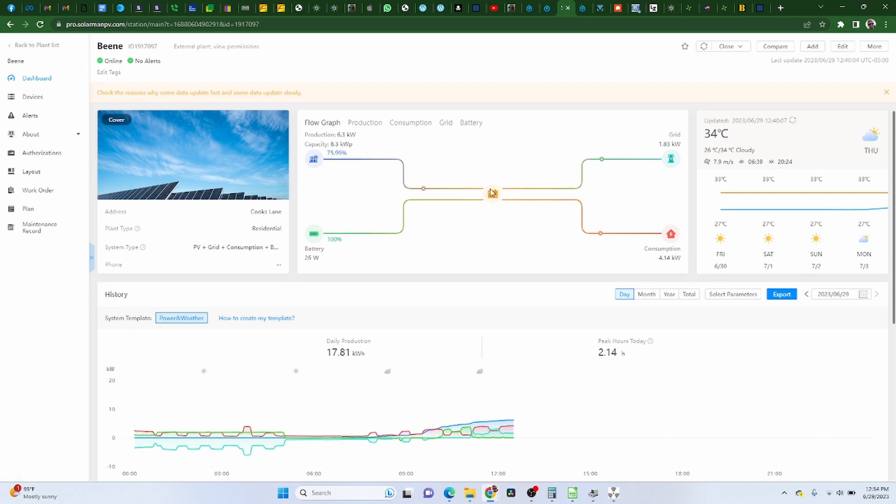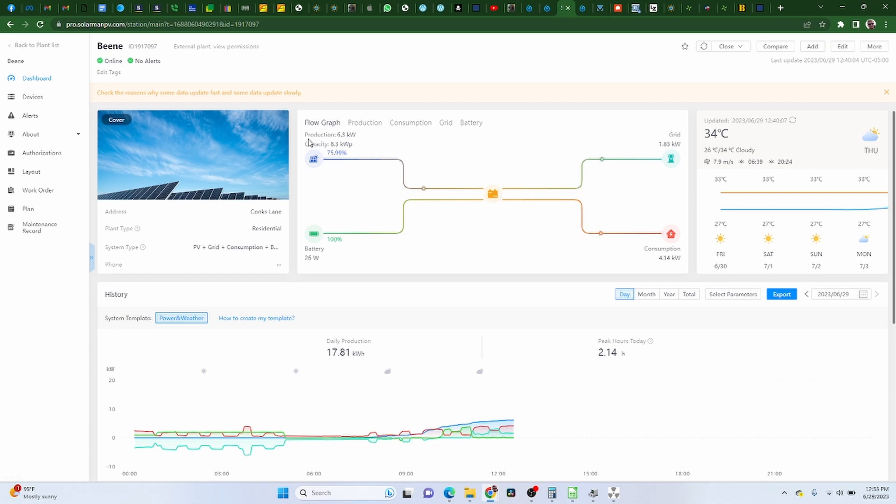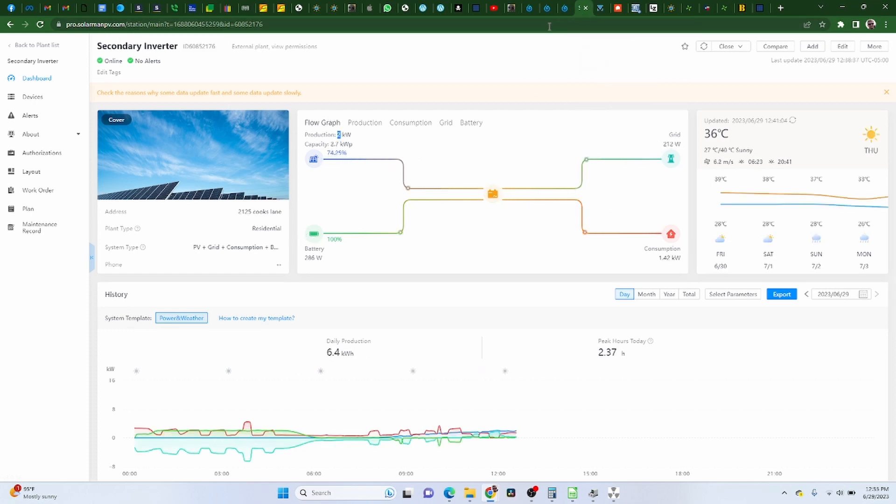Now why is that cool? Because conversion efficiencies. Taking the high voltage DC from the panels and either sending it to the grid or sending it to the loads has a very high efficiency compared to charging a battery. So charging a battery, we might be up at like 90% or 92% charging efficiency. Typically going from this high voltage DC over to the AC is like 95-98%. So by this one doing more of the loads, we're actually getting more power out of the system in general because instead of this charging the battery and then the other inverter taking that battery power back in, we're probably losing 10-15% of our energy by doing that.